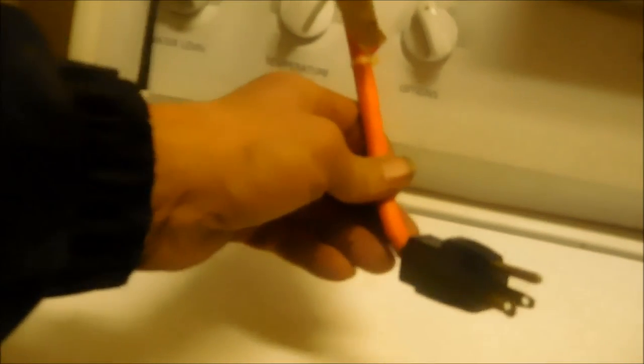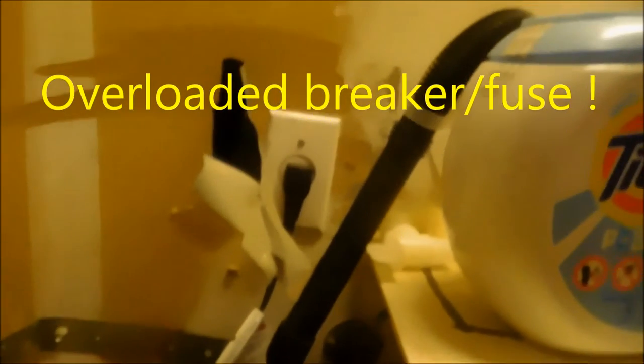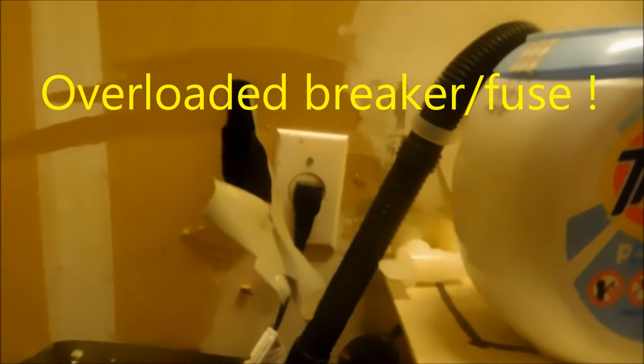So we had this three outlet surge plugged into a one outlet socket with three lines. Now this is the dryer, and this is some heavy duty extension. It goes somewhere to the other room. So this could be a problem. It's not a good idea to run anything more than one plug on a circuit that's designed for only one plug.